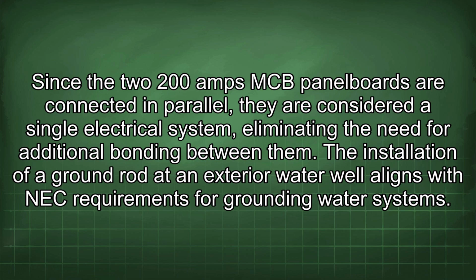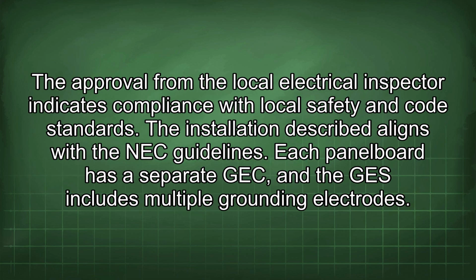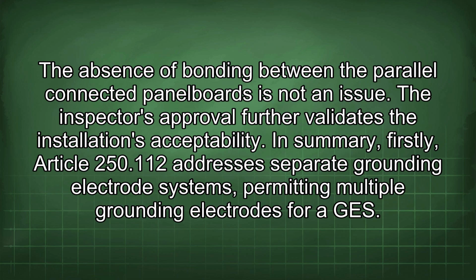The installation of a ground rod at an exterior water well aligns with NEC requirements for grounding water systems. The approval from the local electrical inspector indicates compliance with local safety and code standards. The installation described aligns with the NEC guidelines. Each panel board has a separate GEC, and the GES includes multiple grounding electrodes. The absence of bonding between the parallel connected panel boards is not an issue. The inspector's approval further validates the installation's acceptability.